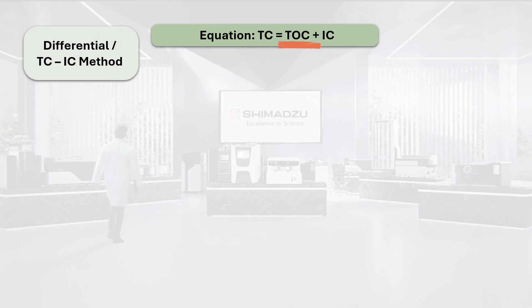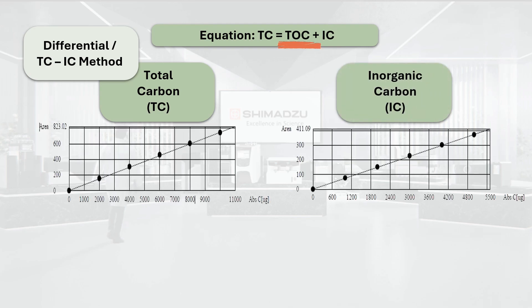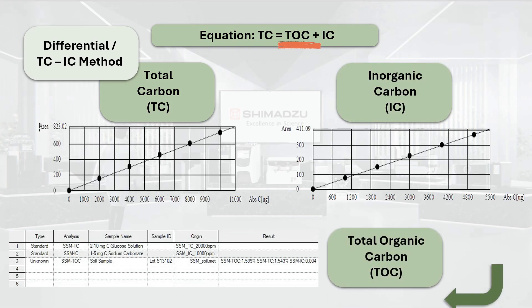To determine TOC content in a solid sample, the differential method is used. In this method, the sample TC content and IC content are obtained from the calibration curve. The TOC value can then be obtained by subtracting the IC value from the TC value. This is how we measure TOC in solid samples using the SSM.